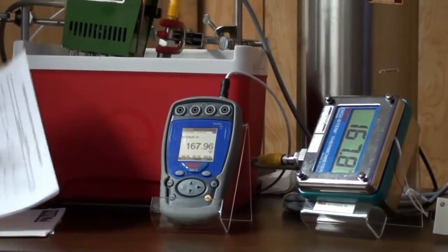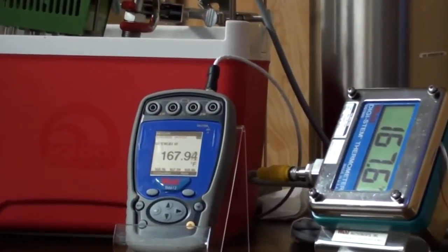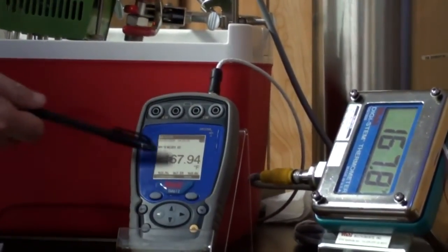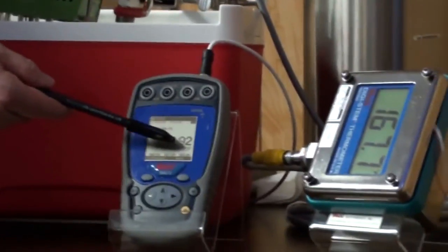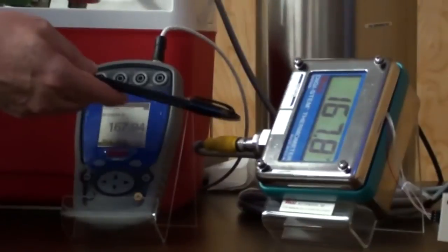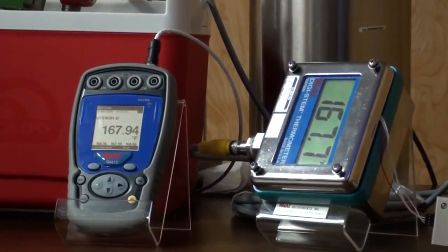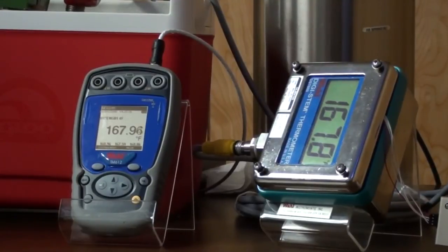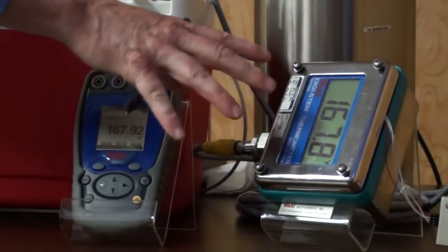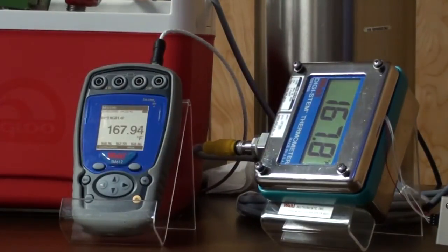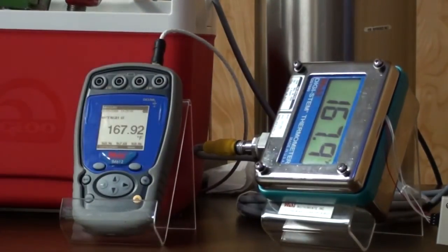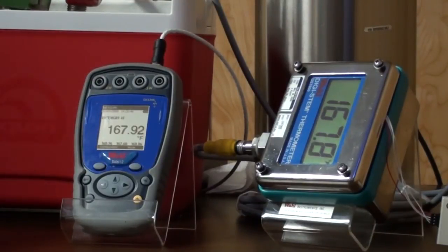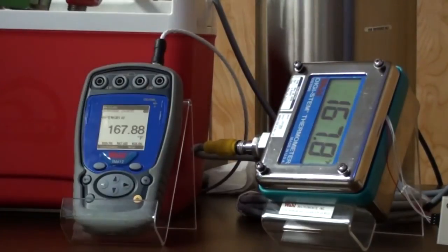So the indicated of the source is 167.94. And this particular meter, I think in Fahrenheit, gives you 0.02 resolution. And our unit under test is 167.8. So I put that there, 167.8. You will see these fluctuating some, so you just have to integrate that yourself or take multiple samples and then average those, however you choose to do that. So in this example with those numbers, our deviation is 0.14. And that's pretty good for the setup that we have here.